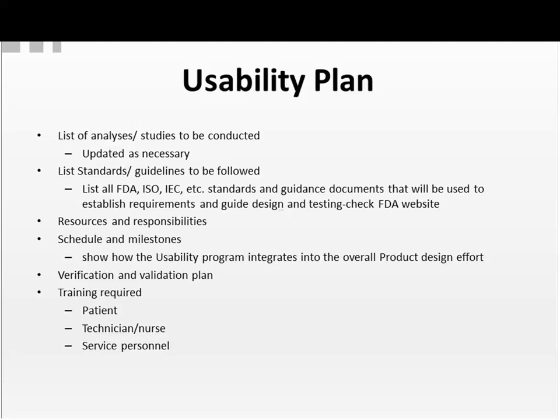And it's important that your plan shows how and when the results of the usability program, the intermediate results, factor back into the design. There should be a mechanism for this, for feedback into the design. There will be a verification and validation plan as part of the usability plan.